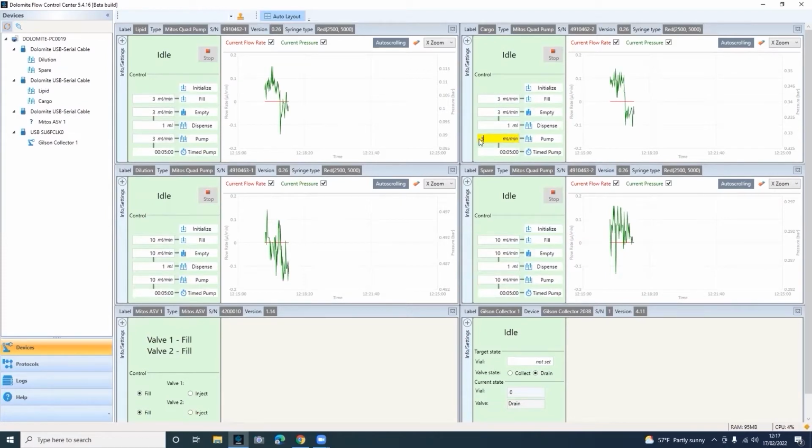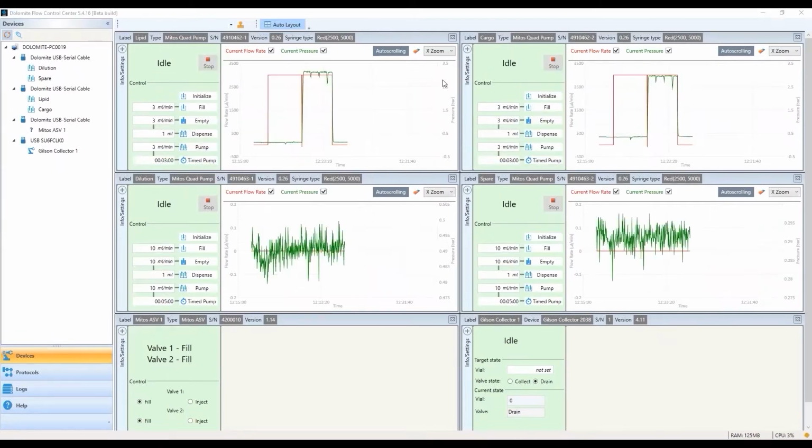Then I'm going to adjust the length of this timed pump input from 5 minutes down to 3 minutes. And once these parameters have been set to your liking, feel free to initiate the timed pump.